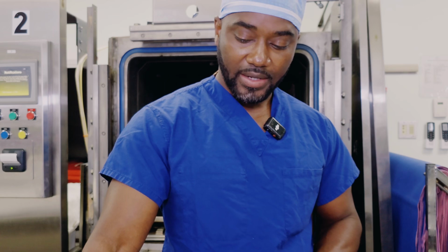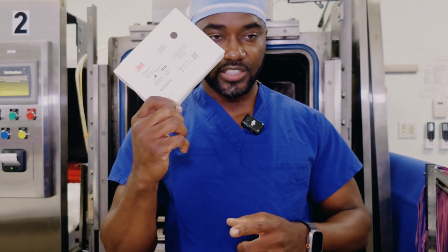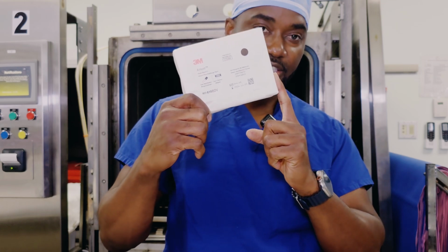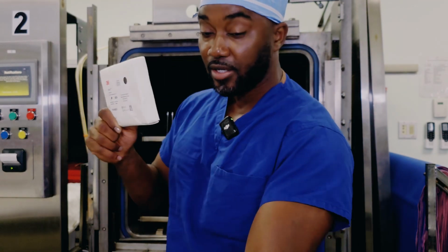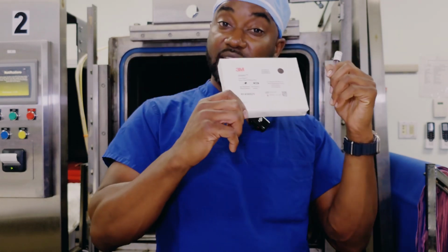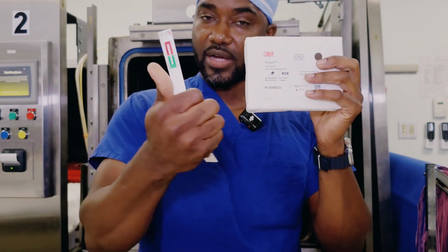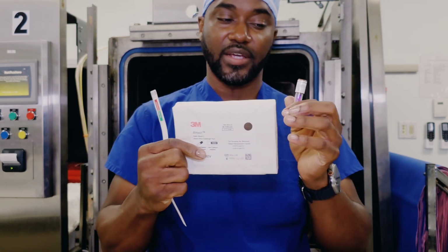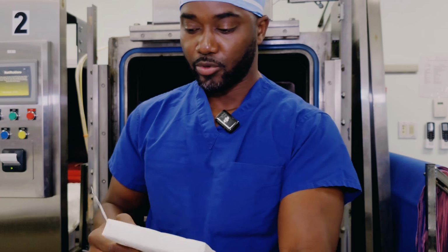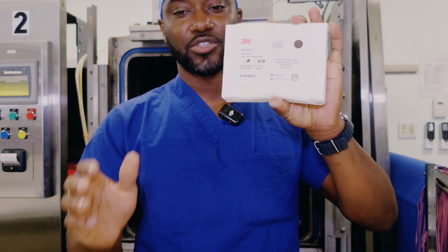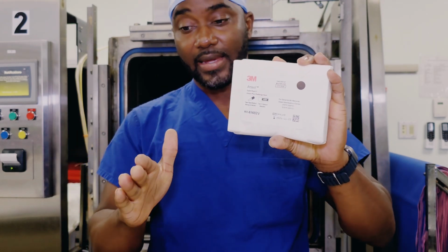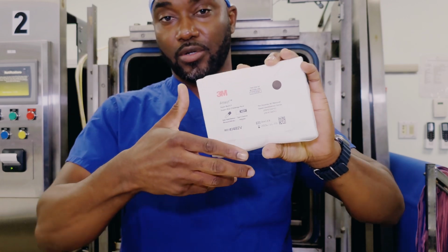Sterilization is never guaranteed. That's why we have to put all of these quality assurance tests. Your process challenge device has an integrating indicator and has a biological indicator to test the efficacy of the load. So within here, you have a type 5 chemical integrated indicator, and you have your Geobacillus spore. Let's open this foil packet to show you what it should look like and what a passing indicator should look like when you open it up.